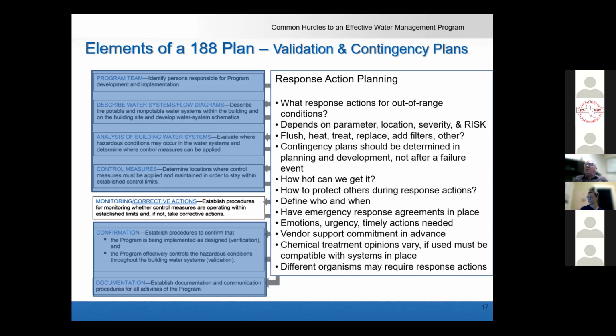Where we're going to go in and we're going to impact that we've got significant problems with bacterial growth and an outbreak of responses. Now we're going to start doing some pretty dynamic things with the system. It requires a lot of coordination, not quite incident command, but it gets towards that level. We've got to define who does what and when they do it. Have your emergency response agreements in place with your vendors. If you've got point of use filters, you need to know what kind of filter you need for your shower heads or for your hand washing sinks. You don't want to start having that conversation and have them telling you, well, this is what we've got for you. You want to know already not only what they have, but what's going to work for you and how many you need and how quickly they can get them to you.